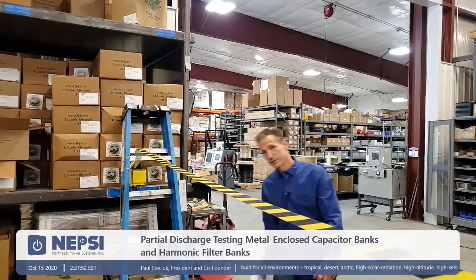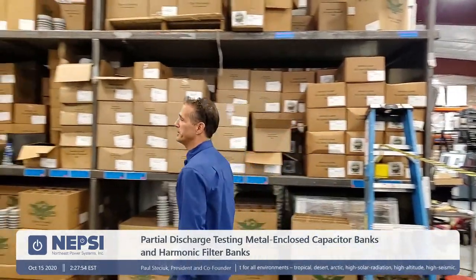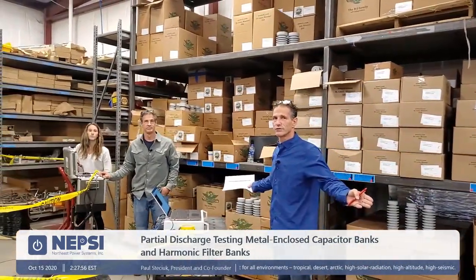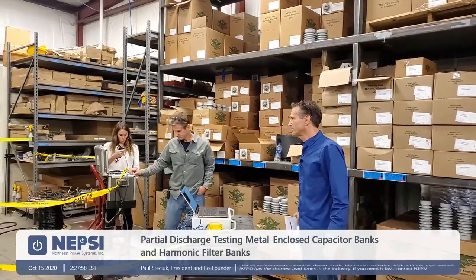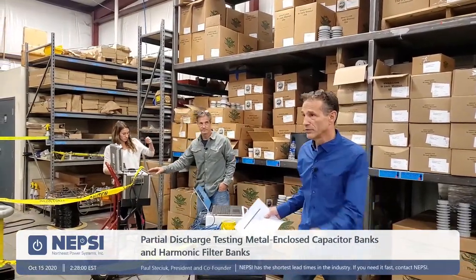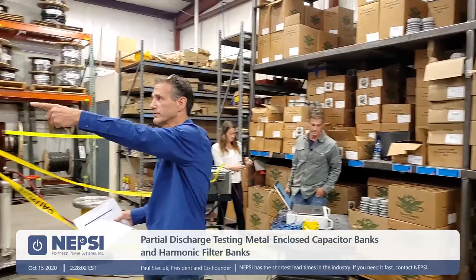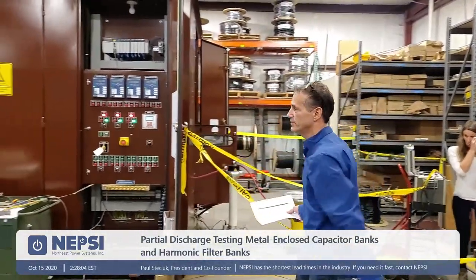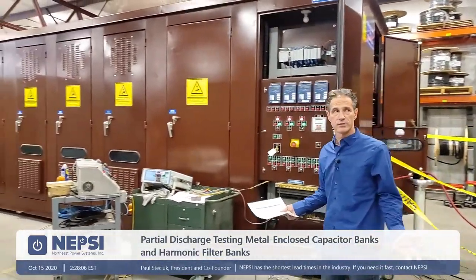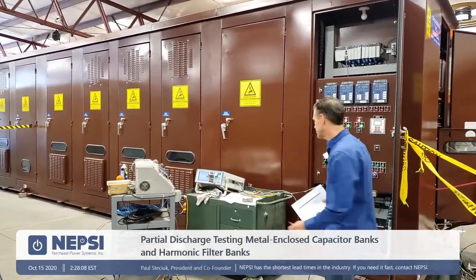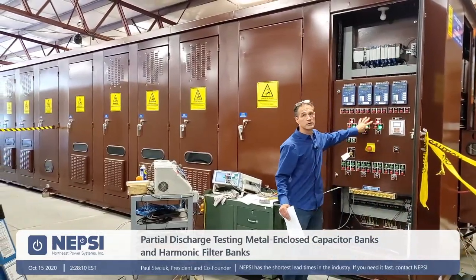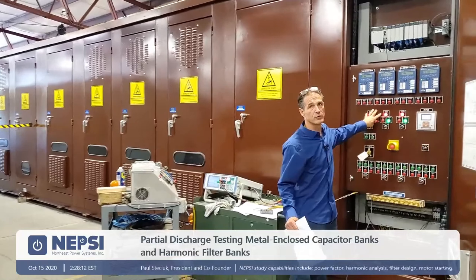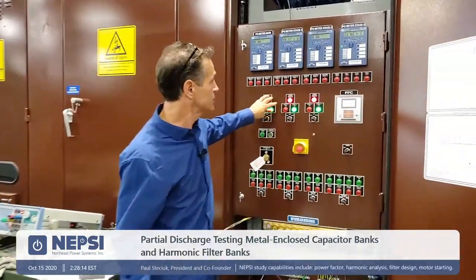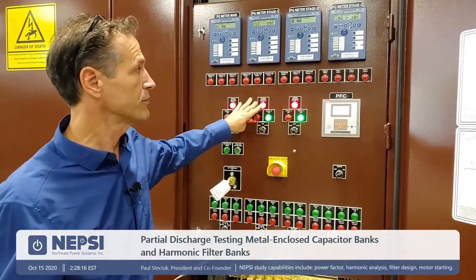Here, are you all set? Yes, I am. All right, so this is the partial discharge setup, the test equipment. We'll just talk about this piece of equipment first. It's 38 kV, 50 hertz, I think it's 20 megavar or something like that. Yes. It's a three-stage bank. This is the control panel. So when we do partial discharge testing, we put the stages in the open position.